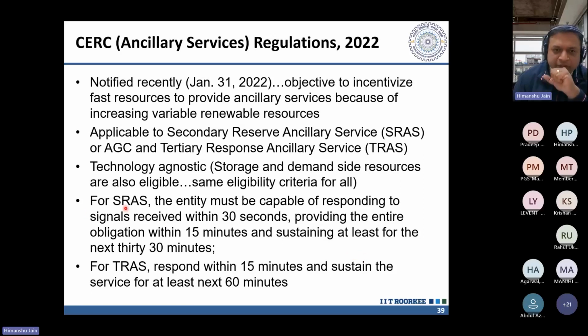The requirement for secondary reserve ancillary service is that the entity providing the service should respond to the signal within 30 seconds, and the entire obligation, the full output it needs to move up or down, should be provided within 15 minutes and sustained for 30 minutes. Those are the criteria you need to fulfill before you can provide the secondary reserve ancillary service from demand side assets, generation assets, or storage assets.